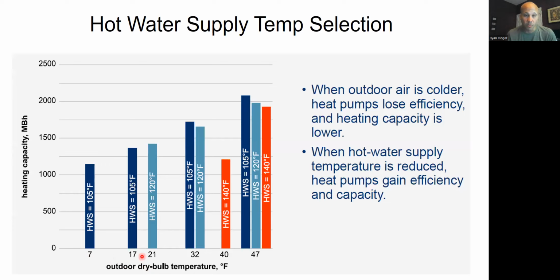But in any case, the warmer the water you make, the easier it's going to be to heat the space. So if it's 47 degrees outside, I could pick any of these water temps and they all could pretty much make me nearly the same amount of BTUs, right? But as the water temperature drops, I mean, I could still make 140-degree water on a 32-degree day. It's just I'm only making this much of it down here instead of somewhere up there. But for all of these, like we showed before, it's going to be dropping off.